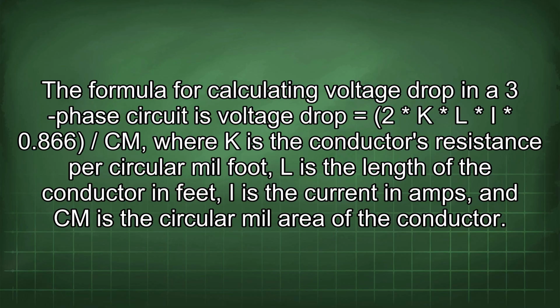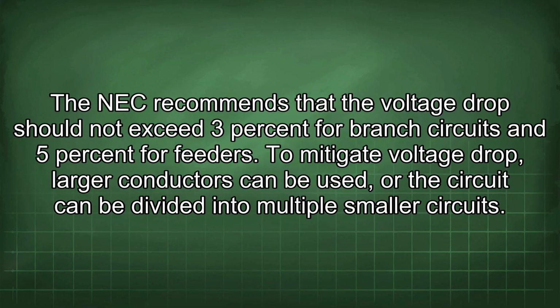The formula for calculating voltage drop in a three-phase circuit is voltage drop equals K times L times I times 0.866 divided by cm, where K is the conductor's resistance per circular mil-foot, L is the length of the conductor in feet, I is the current in amps, and cm is the circular mil area of the conductor. The NEC recommends that the voltage drop should not exceed 3% for branch circuits and 5% for feeders. To mitigate voltage drop, larger conductors can be used, or the circuit can be divided into multiple smaller circuits.